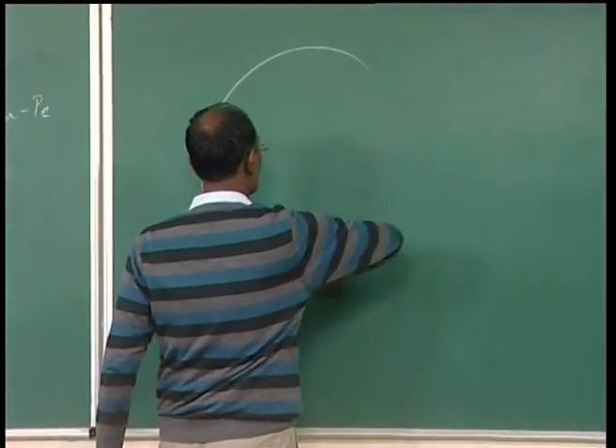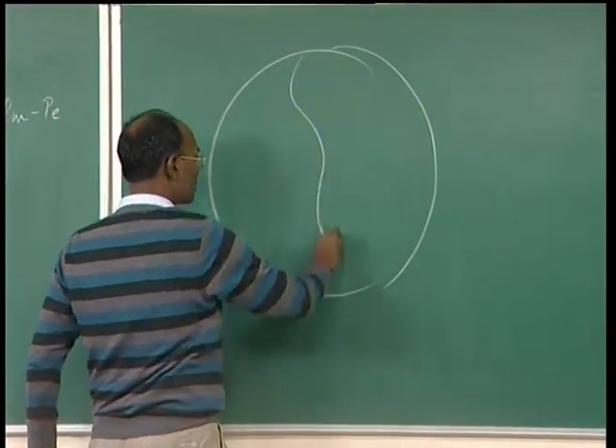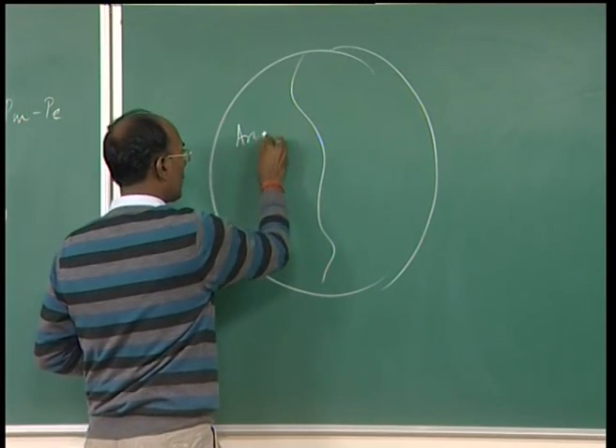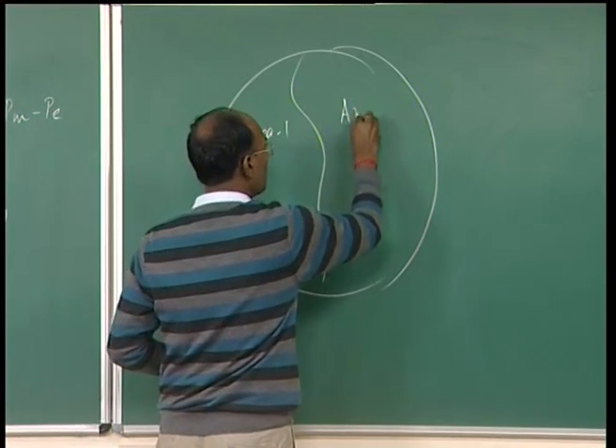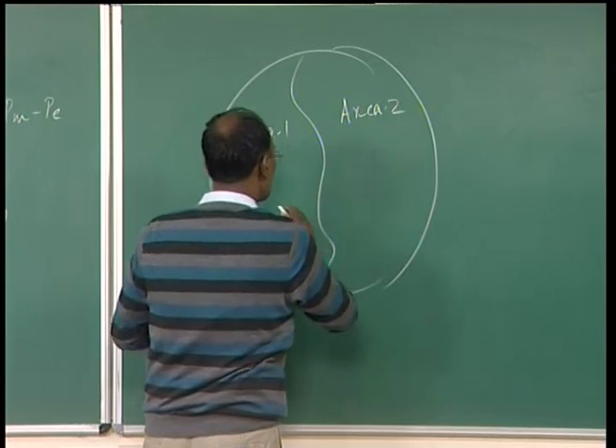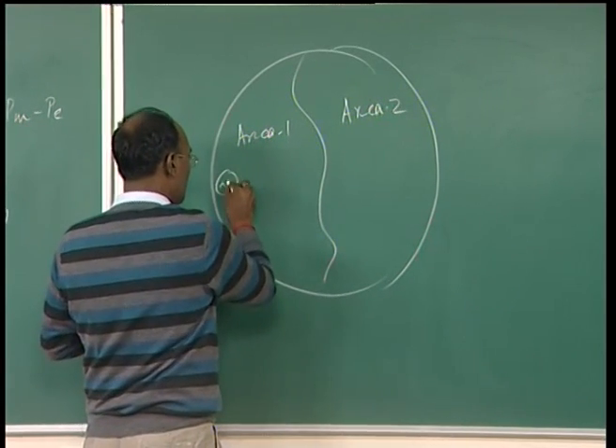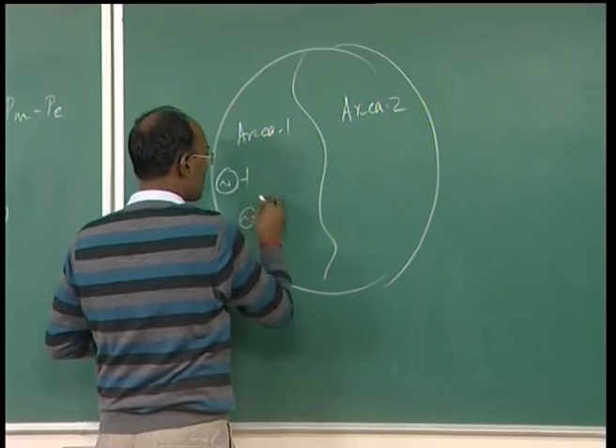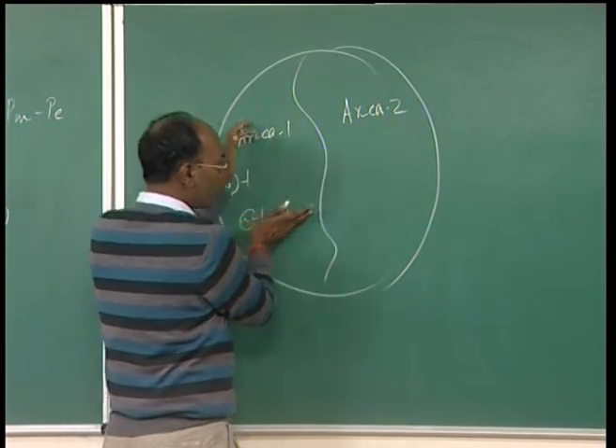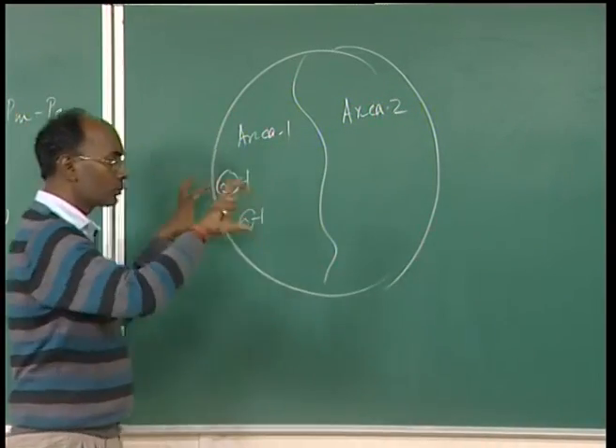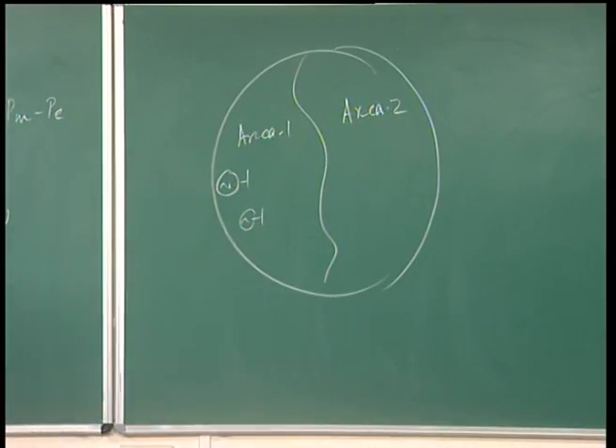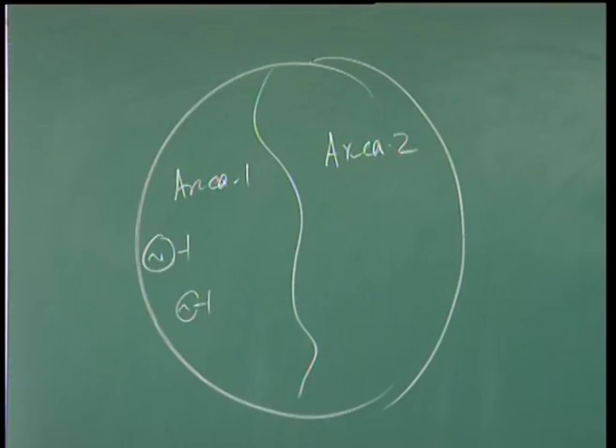Here, in the inter-area modes of oscillation, we have a complete power system which we can divide into two areas. Suppose this is area 1 and this is your area 2. In each area there are various machines connected at the buses, and they are oscillating with respect to the other area. So these two areas are oscillating against each other, and that is called inter-area oscillations. It need not be only two; even three areas can oscillate against each other. So it is called the inter-area modes of oscillation.